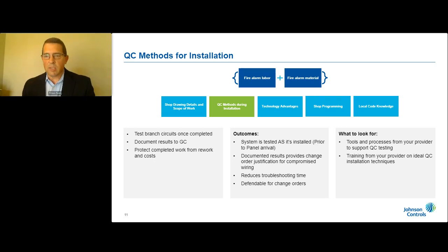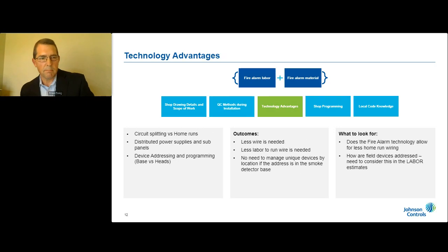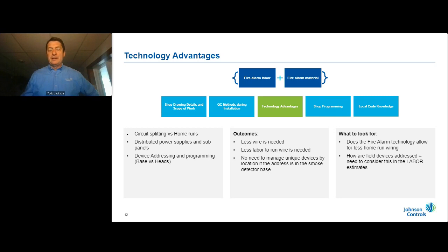So, Todd, let's go to the next slide. Great, thanks Brian. Another thing you should be looking for is technology advantages. What do we mean by that? There's a multitude of great products out there, and they all have different ways of operating with each of the components - the field devices, smoke detectors, pull stations, notification appliances - and they all have a unique way they need to be wired. Many of you on this call have installed all the brands we've talked about. You should be looking for, or understanding, from your estimates, which of the technologies bidding to you require home runs versus being able to split circuits down the middle, so you can tap off of circuits in the middle of a hallway or in the middle of a riser.